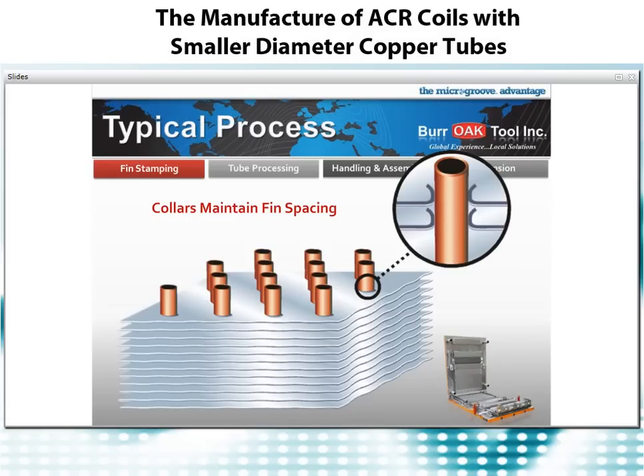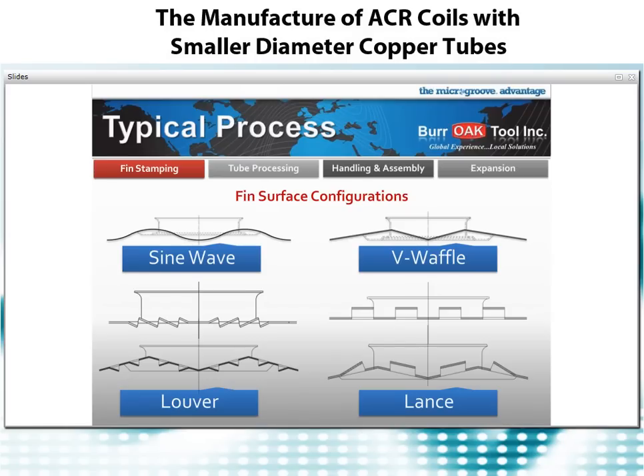Another major requirement of the fin die is to provide accurate and consistent collar heights, as these collars actually establish the spacing between fins. Refrigeration applications may require quite tall collars, increasing the spacing between fins, while air conditioning applications generally use shorter designs. The surface area between the pattern holes is subject to a vast array of designs: some fin configurations are solid with different types of topography such as sine wave and V-Waffle forms. Others use cuts in the fin surface to either redirect airflow or create turbulence to enhance heat transfer characteristics — these are called louvers or lances.